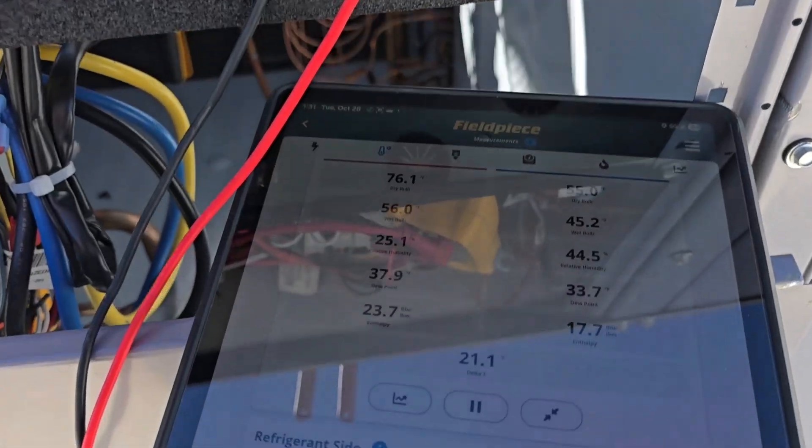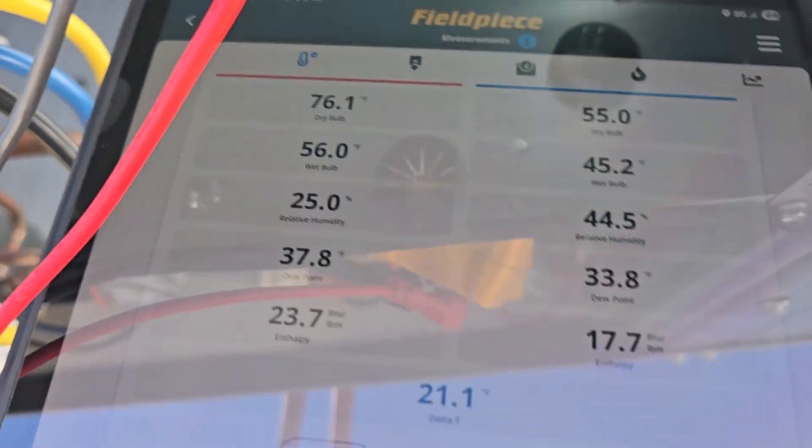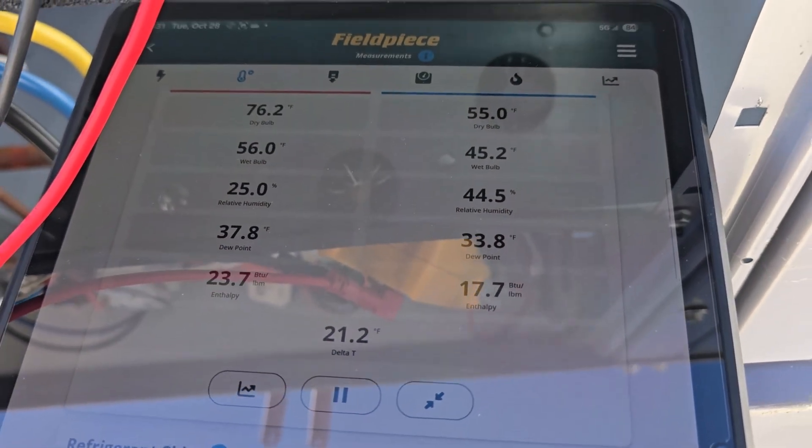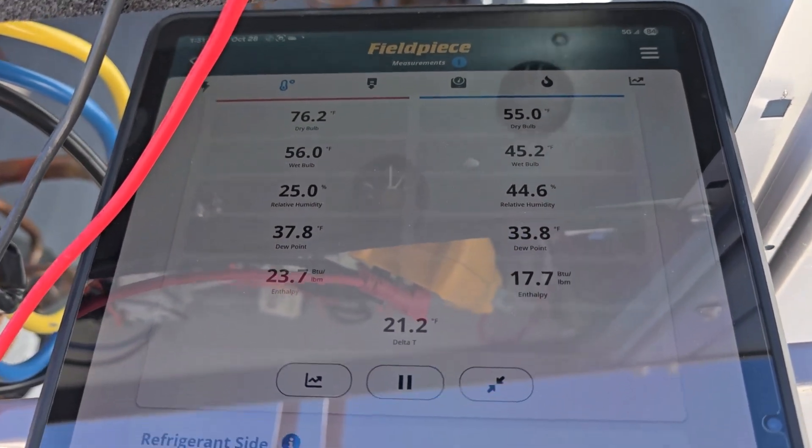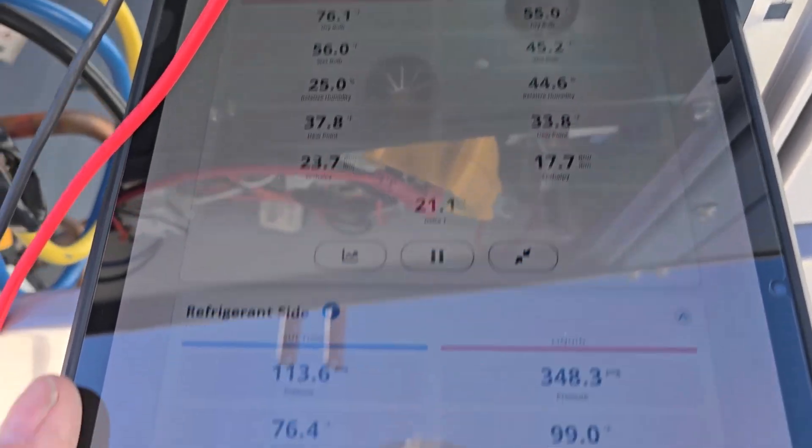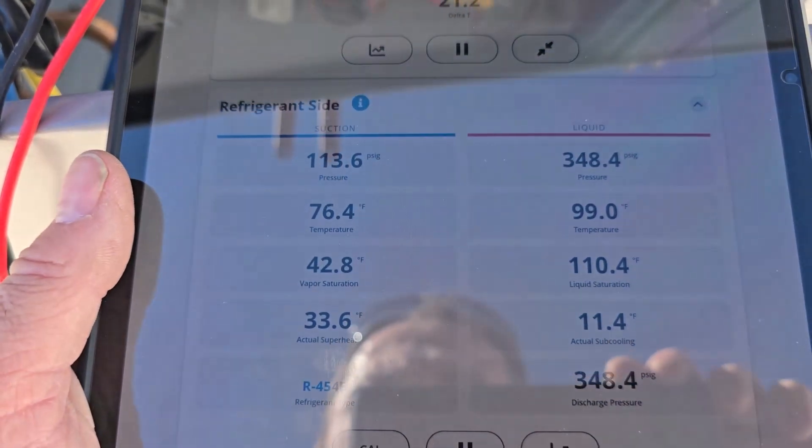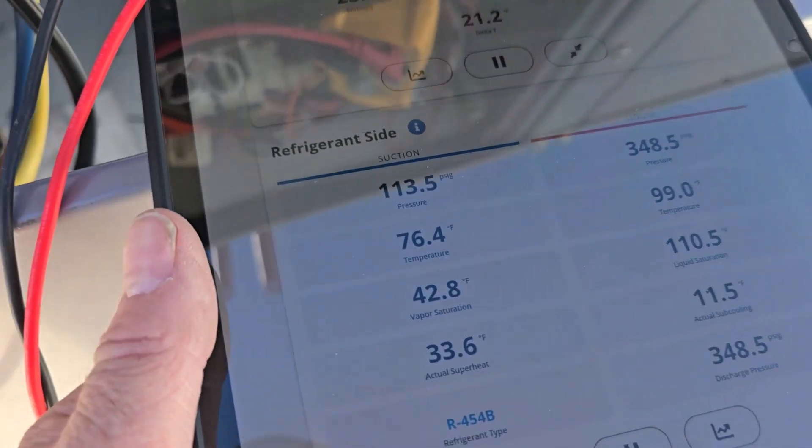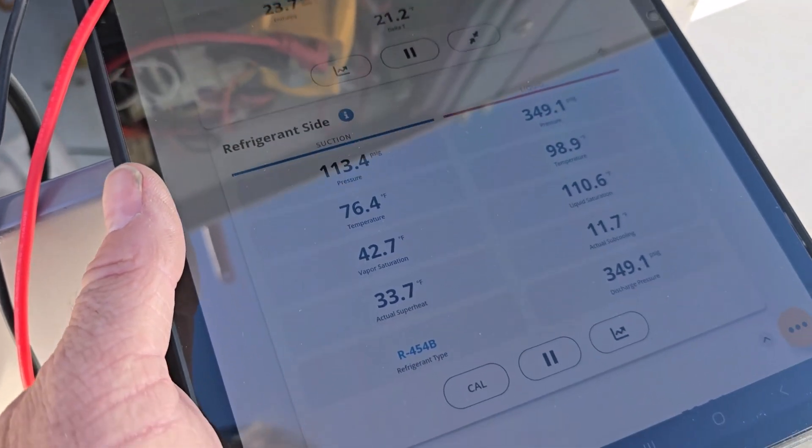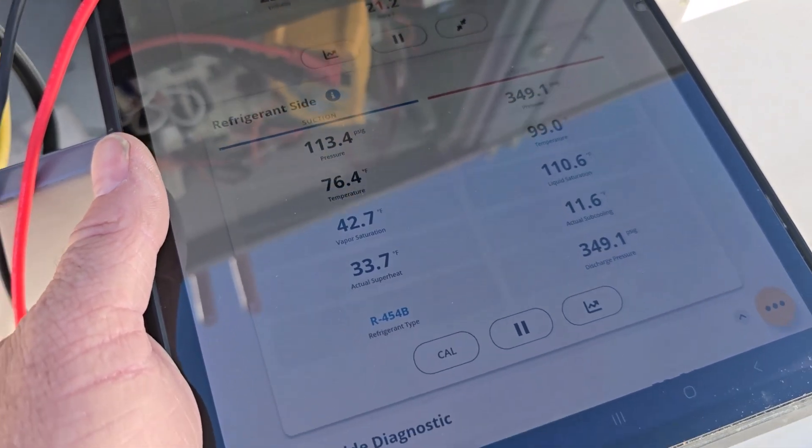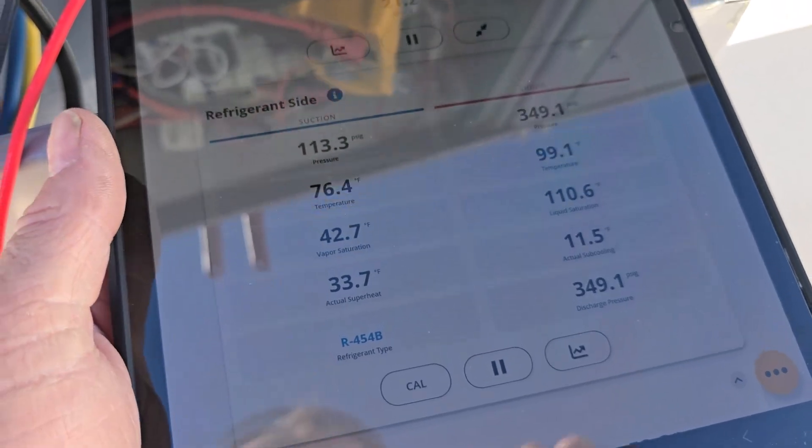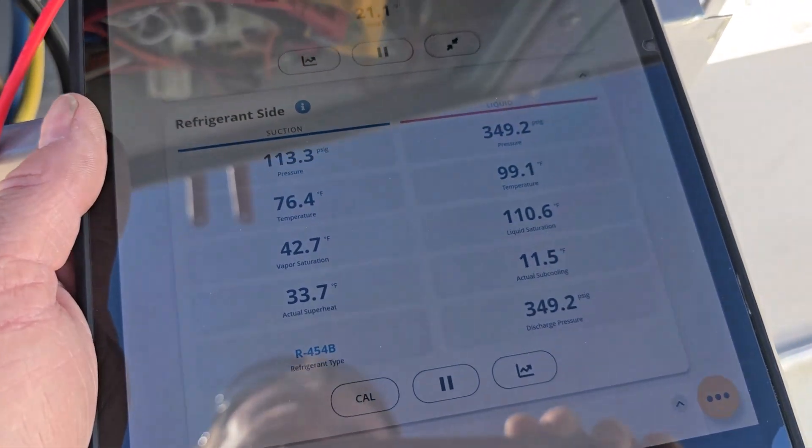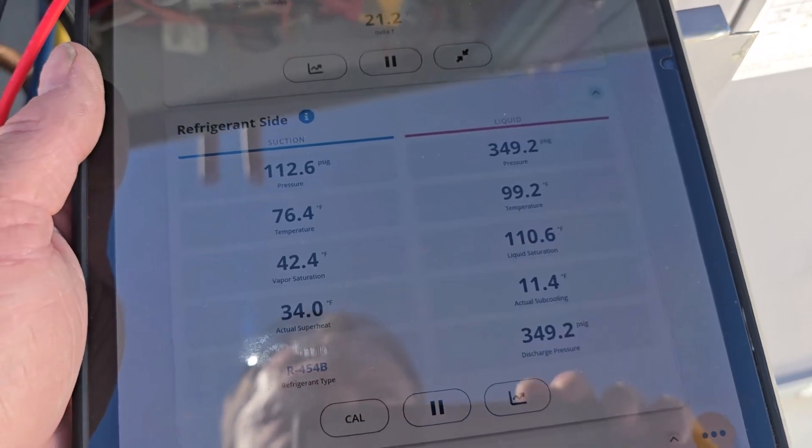So here we go. So now with the second contactor not hotwired to Y1, we got normal, about 21 degrees split temp, normal pressures. Suction came back up to 113. It was nose diving down at like 80 before I unplugged the compressor. This is on R454B. So working out pretty good.